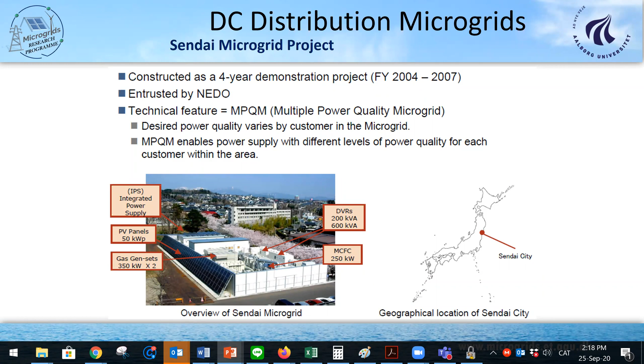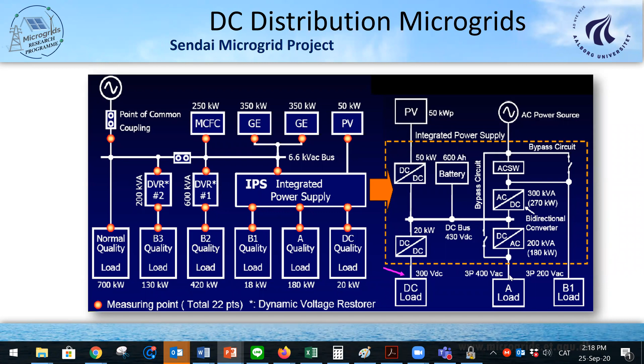This is the electric architecture. It's really like a DC microgrid, because the core is a DC bus of 430 volts, then a battery system, and a number of DC-DC and AC-DC converters to support DC loads and AC loads. In communication, we have a lot of electronic equipment that runs on DC.